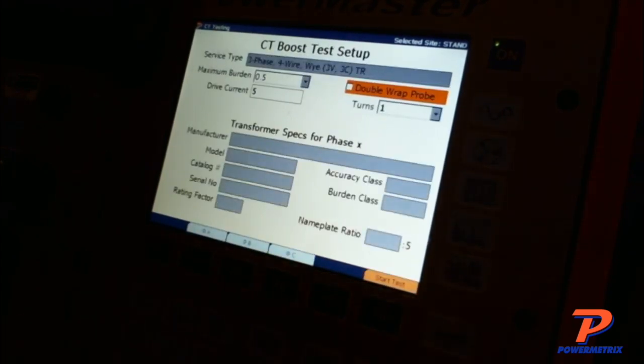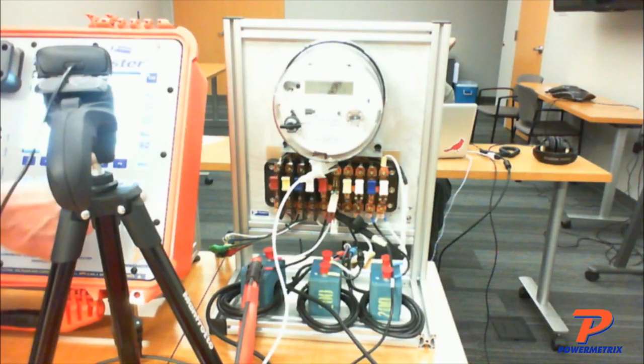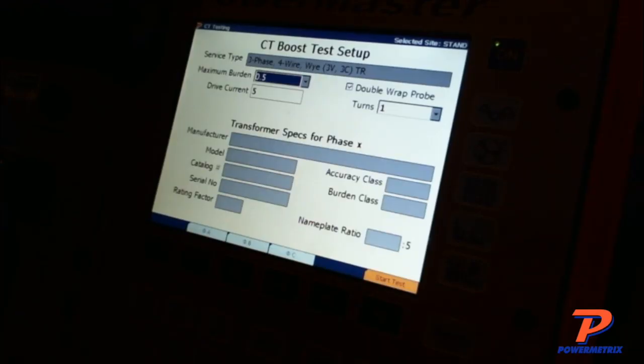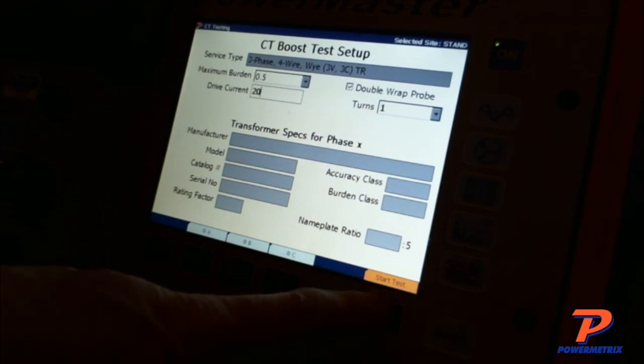Here's where there's some things you've got to add in now, because I'm actually doing this at the site, so I have my flexes involved. I did double wrap my flex, so I'm going to check that double wrap box. Max burden looks okay, I'm going to leave it at 0.5. Drive current, I'm going to put 20 through there. And I only put one turn through, my drive cable only went through one time, so I'm leaving that as 1.